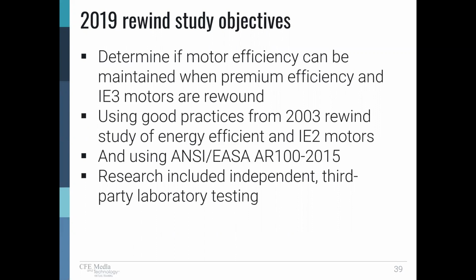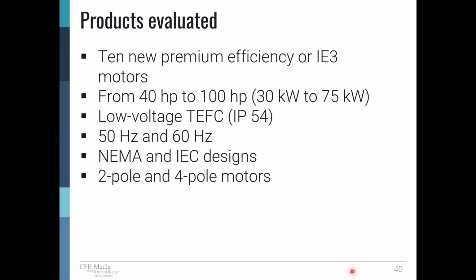And the research that was to be done included independent third-party laboratory testing of the efficiency of the motors. The products that were evaluated: 10 motors, premium efficiency IE3, 40 to 100 horsepower, low voltage, totally enclosed fan cooled. They were all low voltage, meaning any motor that's rated up to 1,000 volts. And they were 50 hertz and 60 hertz.